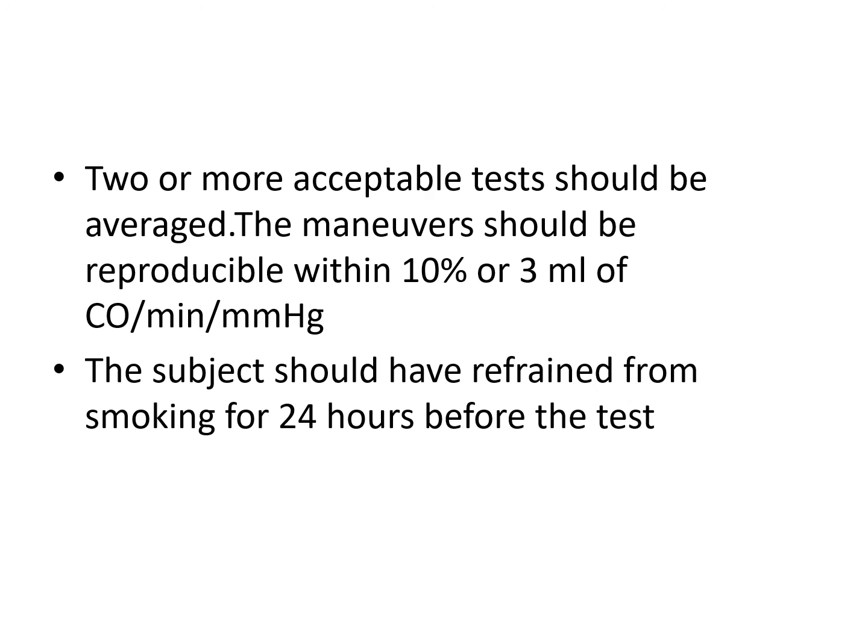Two or more acceptable tests should be averaged, and the maneuvers should be reproducible within 10% or 3 ml of carbon monoxide per minute per millimeter of mercury. This indicates that there is rough agreement, and the subject should have refrained from smoking for 24 hours before the test. If all these parameters are met, then the test is assumed to be adequate.